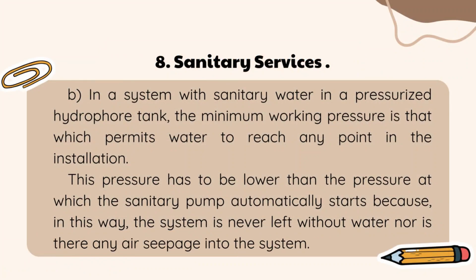B. In a system with sanitary water in a pressurized hydrophore tank, the minimum working pressure is that which permits water to reach any point in the installation. This pressure has to be lower than the pressure at which the sanitary pump automatically starts because, in this way, the system is never left without water nor is there any air seepage into the system.